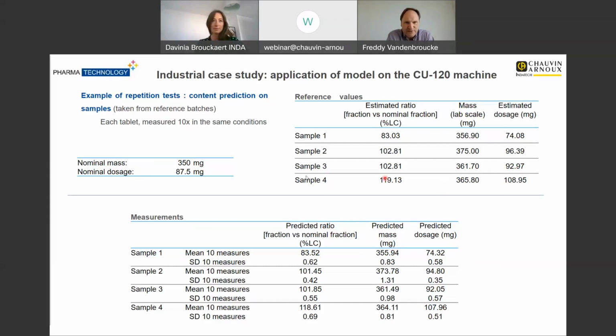Each tablet has been measured 10 times by the CU120, and we see the statistics at the bottom of the slide. The prediction values are close to the reference values, and the standard deviation of the fraction ratio is below half of the RMSEP. The standard deviation of the masses is around 1 milligram. But what finally matters is the amount of drug that each tablet contains, and here also the results are close to the reference values with a quite tight standard deviation. Bottom line, we can say that the machine is capable of precise and accurate measurements related to content uniformity.